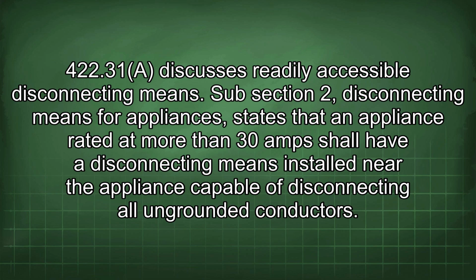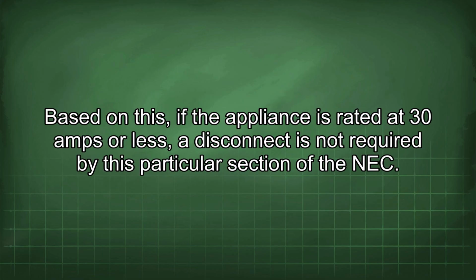Subsection 2, disconnecting means for appliances, states that an appliance rated at more than 30 amps shall have a disconnecting means installed near the appliance capable of disconnecting all ungrounded conductors. Based on this, if the appliance is rated at 30 amps or less, a disconnect is not required by this particular section of the NEC.